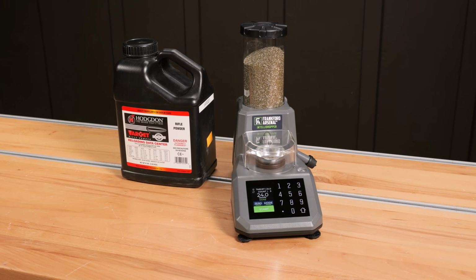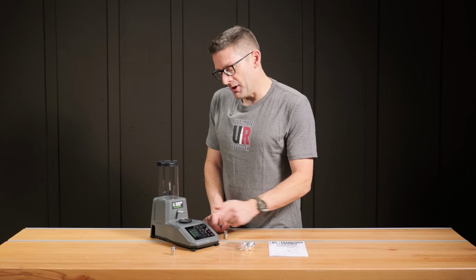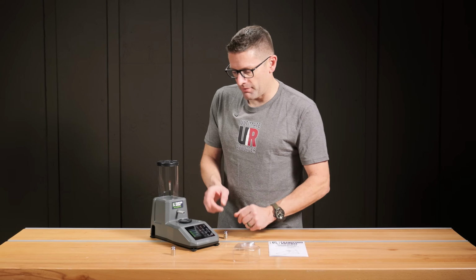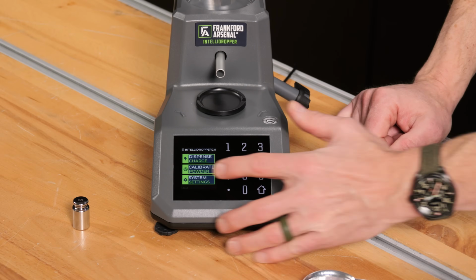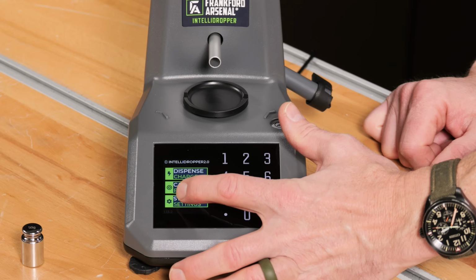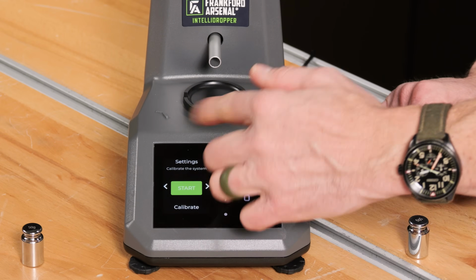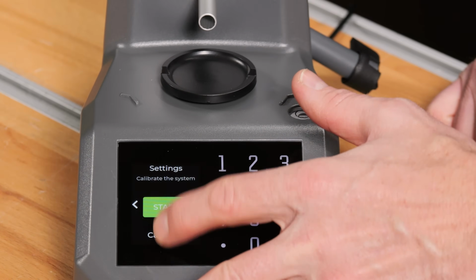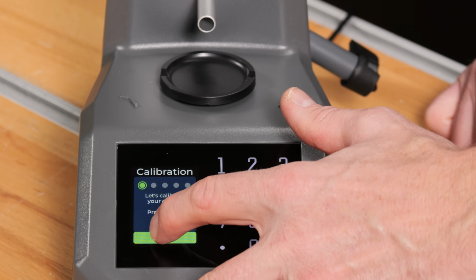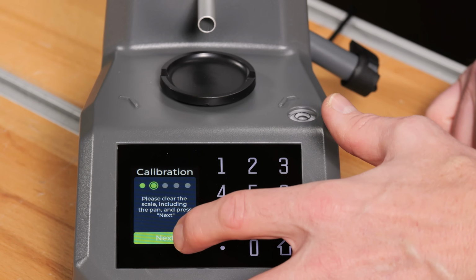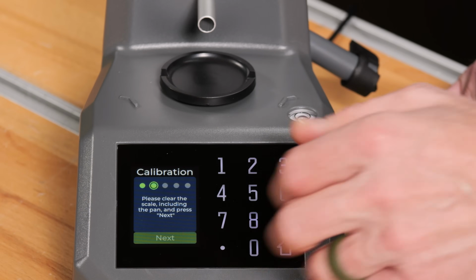All right, before we fill the powder dispenser with powder, we're going to go ahead and calibrate the scale now that we are warmed up. So I've cleared the platform. We've got the dust shield off. I pulled out the 50-gram weights, and we just go right into the system settings menu here. Pulls up the calibration screen. We hit start, and then that's going to start us through the flow. Start takes us to the first instruction, clear everything. Next.